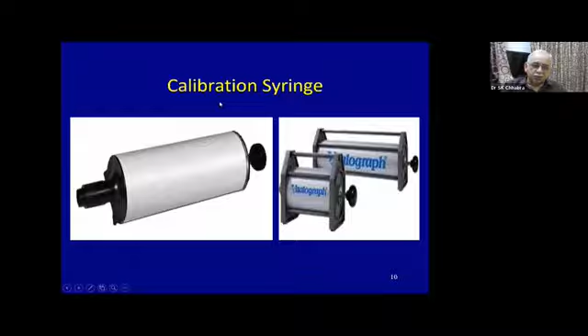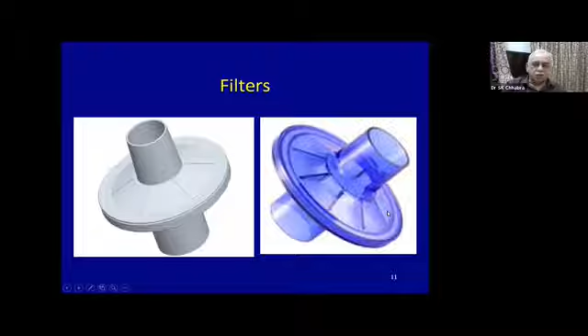So this is very important, and any equipment that you buy, you should always buy a calibration syringe, although it will cost a few thousands more. But maintenance of equipment requires a calibration syringe. Then you require filters. Filters are very important at all times because there's always a risk of transmission of infections. And it was not only in the COVID era that we became conscious of this. Earlier also we have been using these filters because the person exhales his air into the spirometer. If a filter is not there, there is a chance that the microbes may get into the machine, especially if it's a closed system. But a pneumotach based machine is an open system, so the risk of infection is minimal. But still, these filters are used, and these are not very expensive.